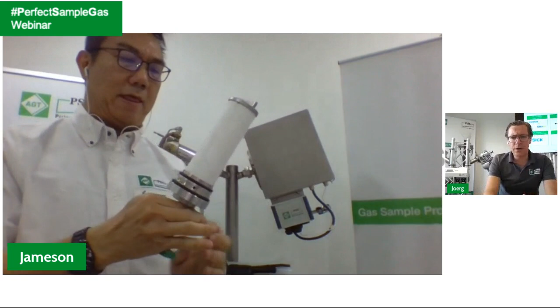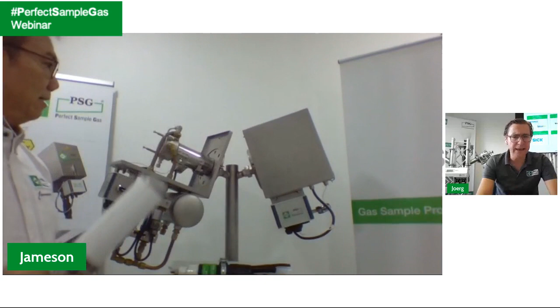filter. So again, maybe for the people who are not that experienced, we have two probes there. We can see it's a PSG basic, and what you are now showing here is the PSG plus probe, right? Yes. And we are talking here about a technology which allows cleaning the probe by itself, right? So no one has to climb up and no one has to change the filter. So by using this back purging, it's capable of reducing the maintenance effort. But you have to explain to us how that works with the filtration.